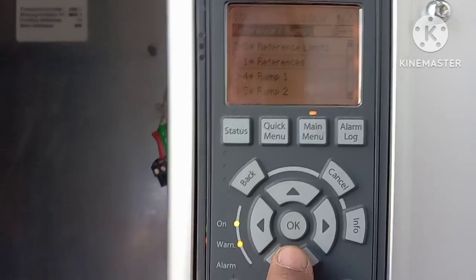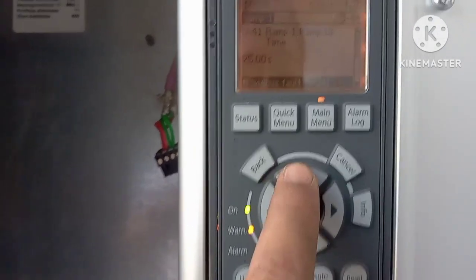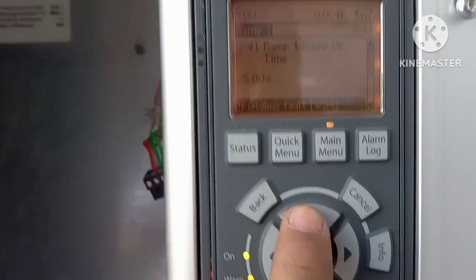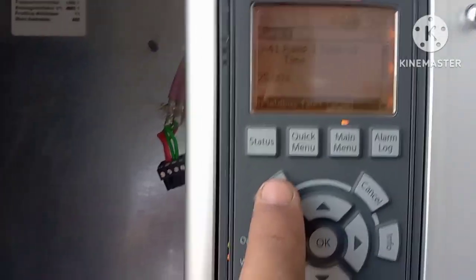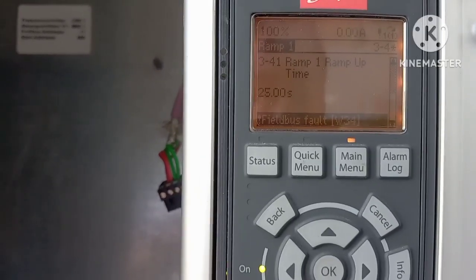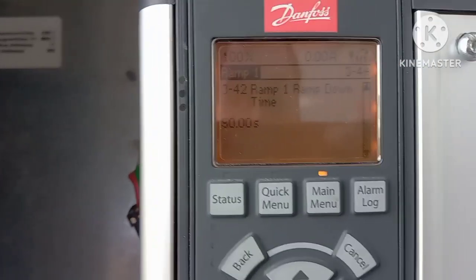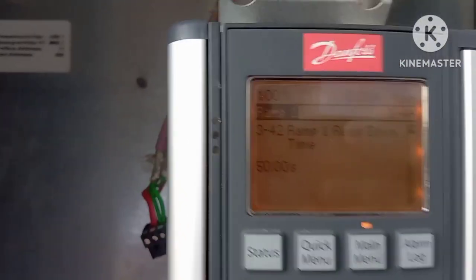Under Ramp 1, you can change acceleration and deceleration. This is the ramp-up time — you can change the acceleration time from here. And here is the ramp-down time. Parameter number 3-42 is shown on screen.